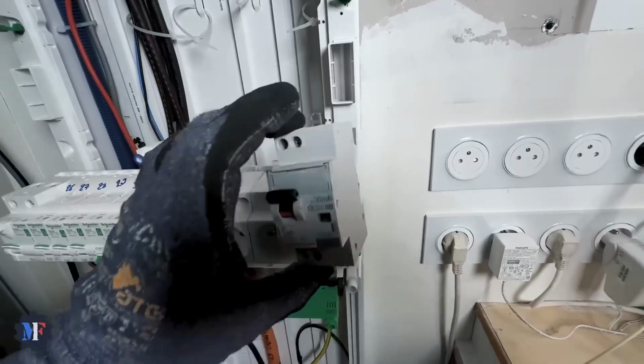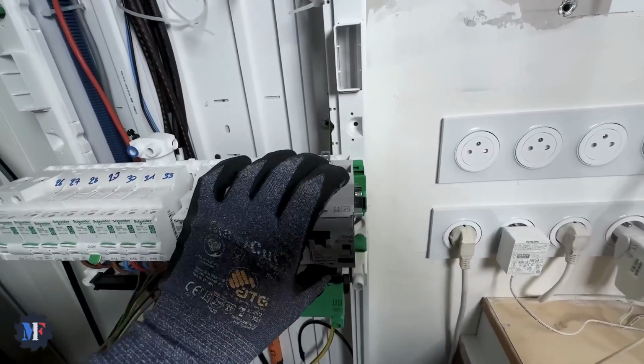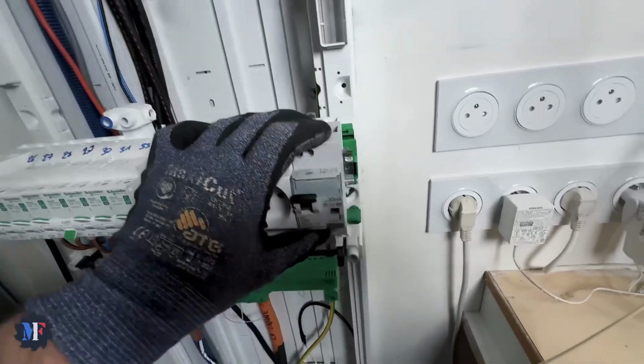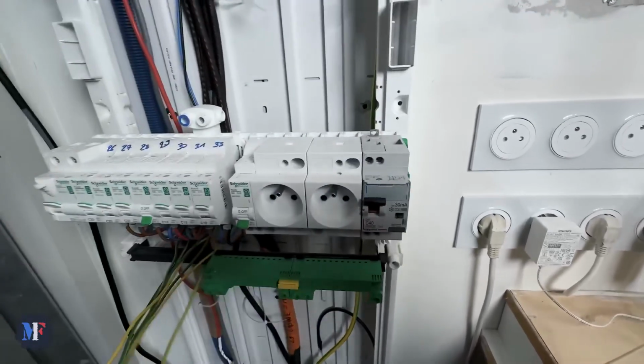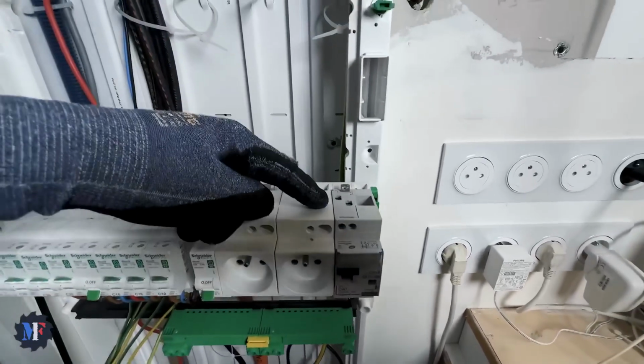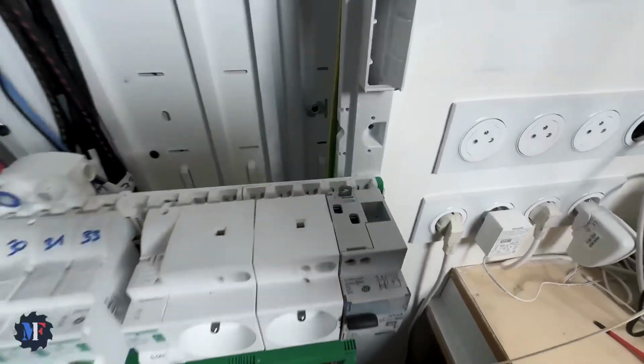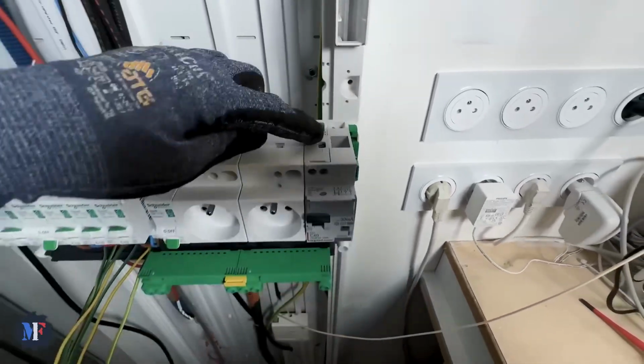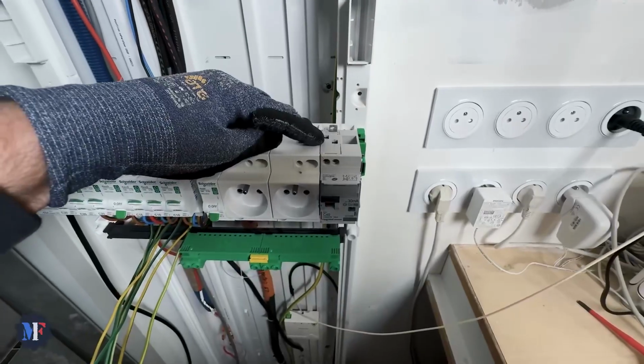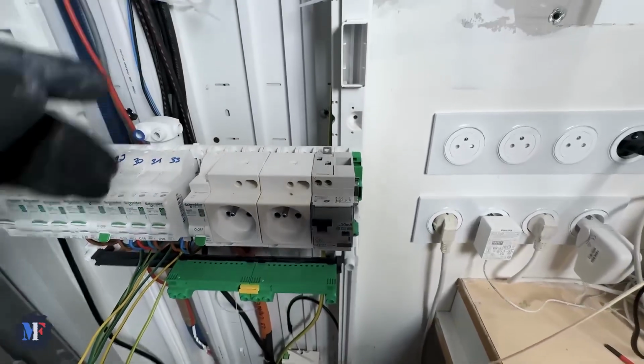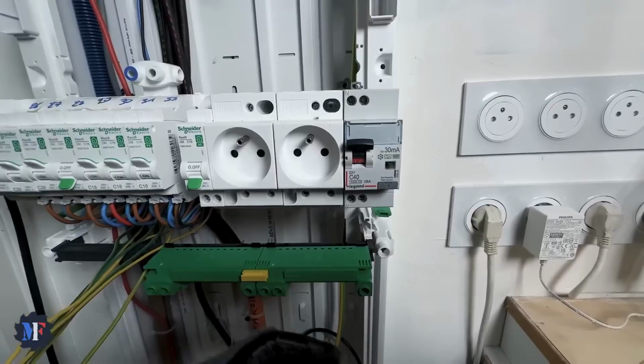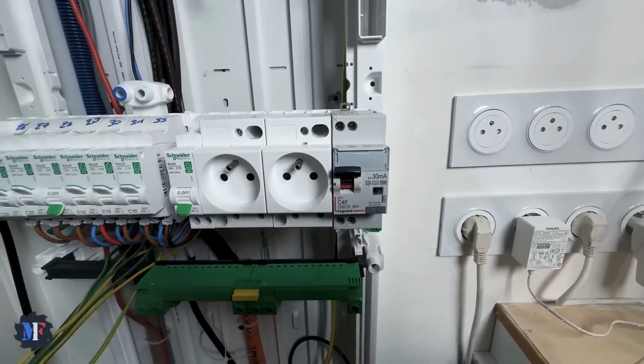And I'm going to install the differential circuit breaker for the charging station, if I can manage to hook it up. There we go, perfect. This one must be connected directly with 16mm2 cable, not to the distribution comb or plug-in. I connected directly with 16mm2 cable to the phase neutral block. And underneath, we'll connect the ground and wire up the charging station.